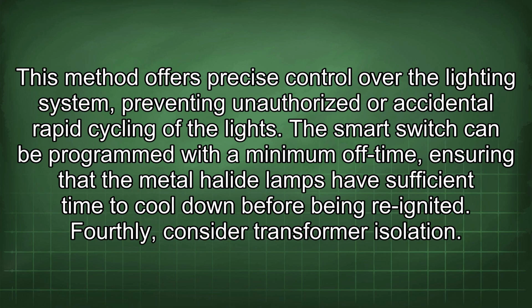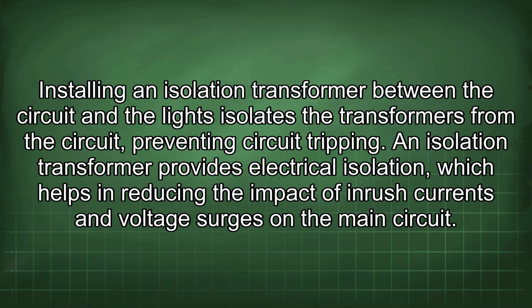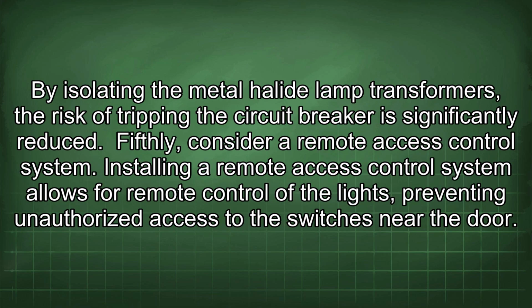Fourthly, consider transformer isolation. Installing an isolation transformer between the circuit and the lights isolates the transformers from the circuit, preventing circuit tripping. An isolation transformer provides electrical isolation, which helps in reducing the impact of inrush currents and voltage surges on the main circuit. By isolating the metal halide lamp transformers, the risk of tripping the circuit breaker is significantly reduced.